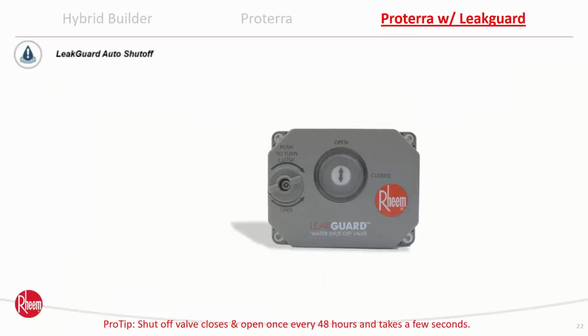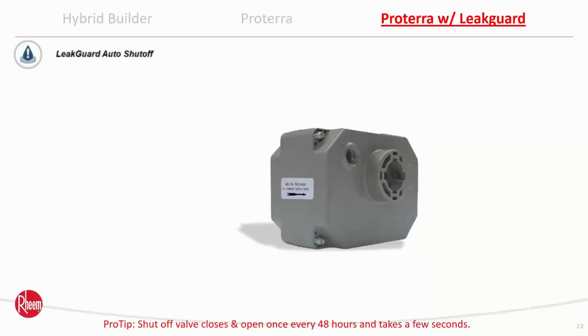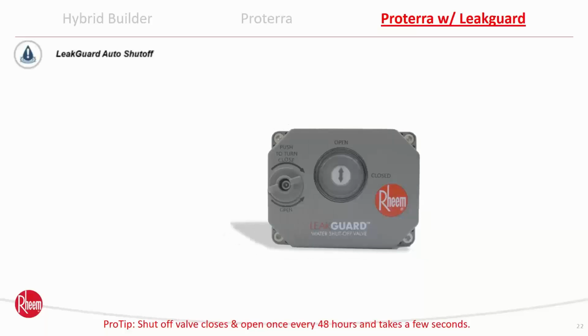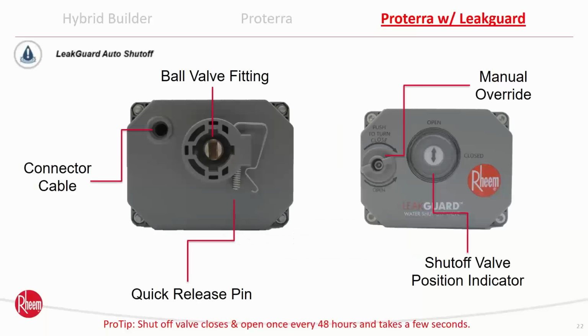The valve itself, this is the controller for the valve. It's a standard ball valve on the heater. If you look at the back of it, this square fitting right here goes down over that ball valve, and that's how it controls the valve itself. This clip right here is a quick release pin, so if this actuator goes bad for some reason, all you do is pull this clip, lift the actuator off the valve, unplug it, and you can replace the actuator. So it's a quick, easy replacement.